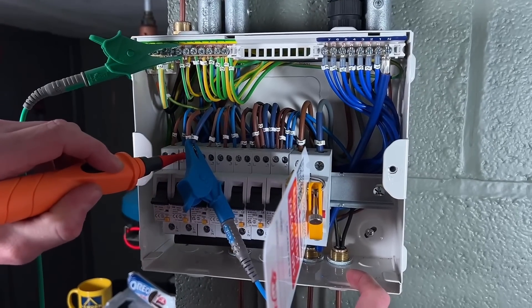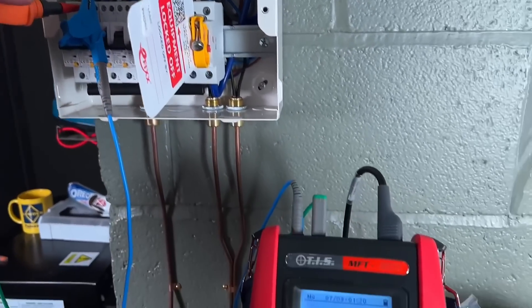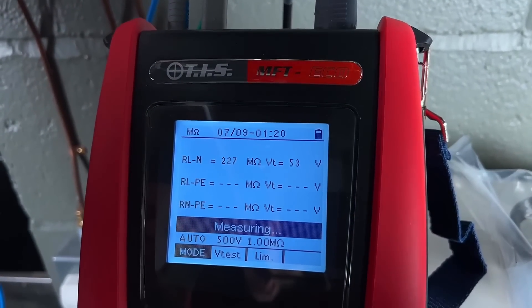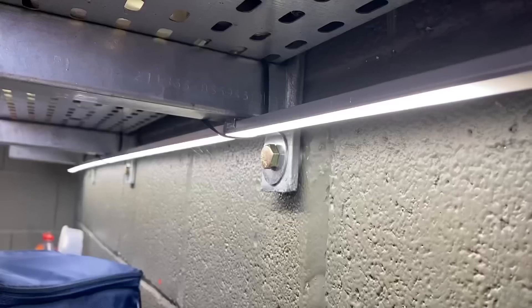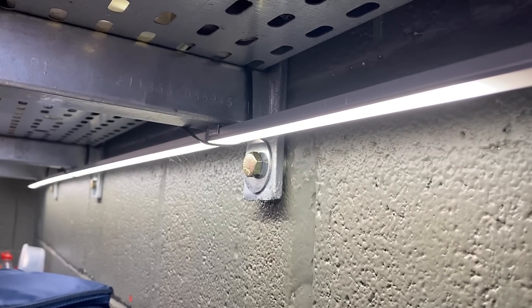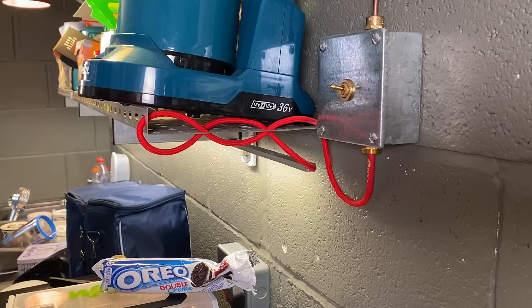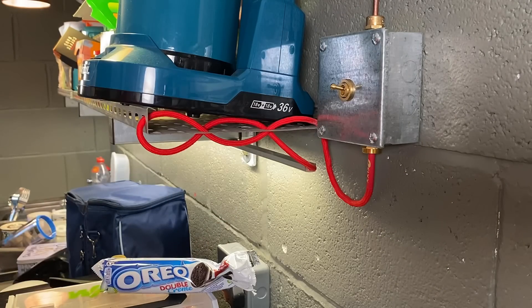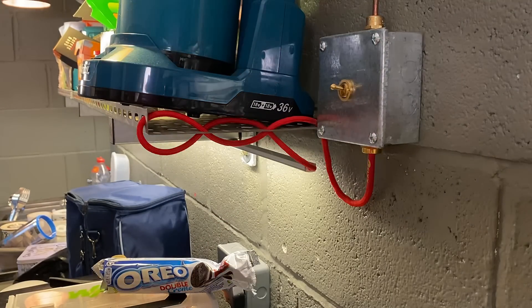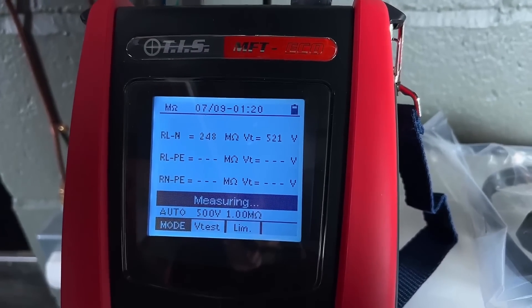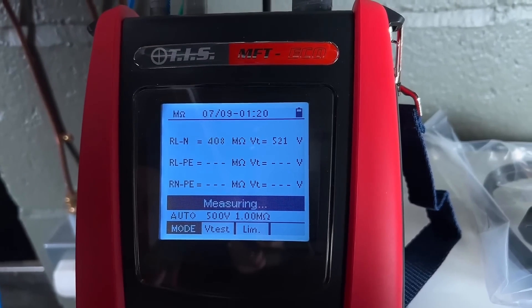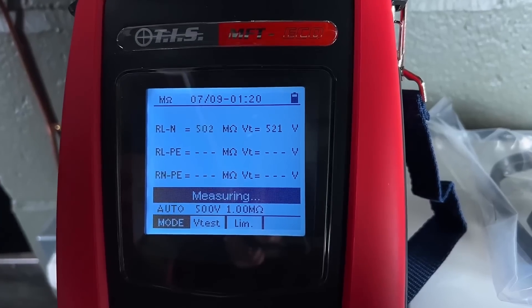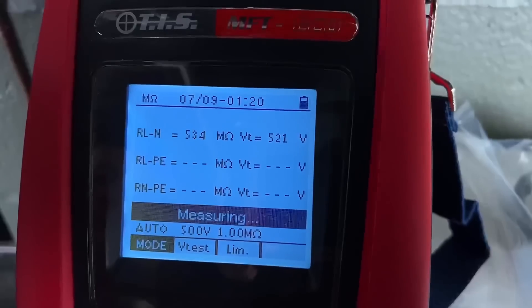What's that over there guys? Let's repeat the test again. Press and hold the button, we should hear a click and we're underway. But what's really nice about that first test about the MFT eco, it held back that voltage meaning that we didn't damage the LED strip that Rick forgot to turn off. And the keen-eyed amongst you will have noticed the switch is in the wrong way around, so up is on and down is off. I'll be having a word with Rick in the future about that one. And we can see now with that load been removed, we're cycling through first of all our line and neutral, just again checking that Rick hasn't left anything else in circuit.